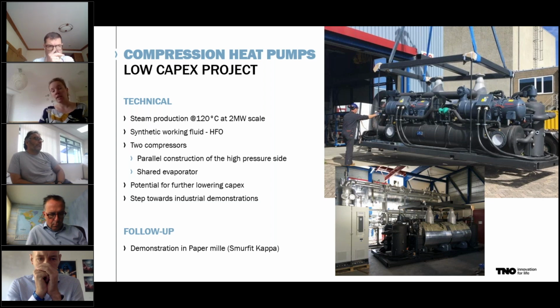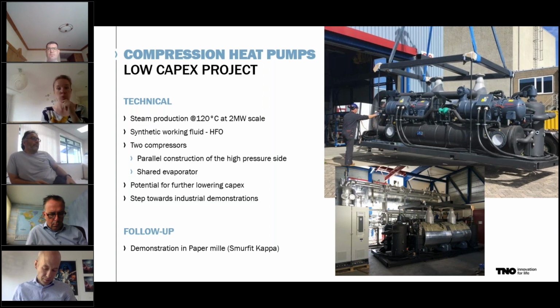In this design, there are two compressors constructed in parallel on the high pressure side. You can see the gray cylinders that are the tops of the two compressors, and they share an evaporator. With the design we have now, we think there's even potential to lower the CAPEX further if we would be able to make this one compressor and one evaporator. But in this project, this was the best option to go for.